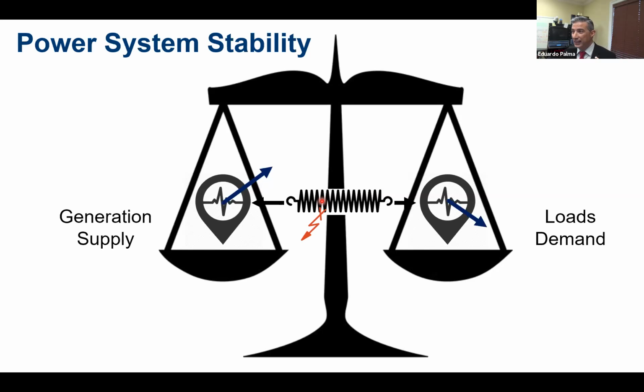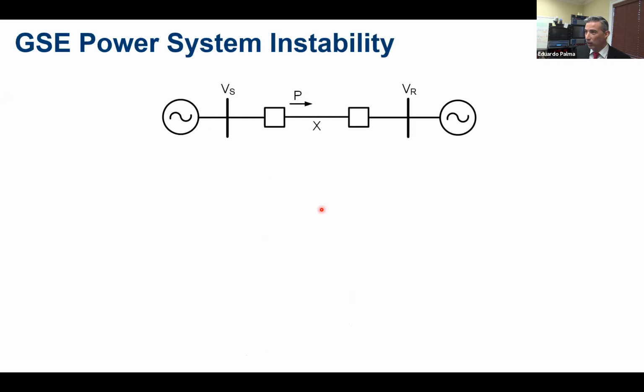When there are system faults through the transmission lines, this causes us to need to compensate the system in order for it to keep stable. But the compensation, specifically in power systems, needs to happen in milliseconds. Millisecond reaction times are a must, or they are required in system specifications when it comes to protecting a wide area network or a whole country.